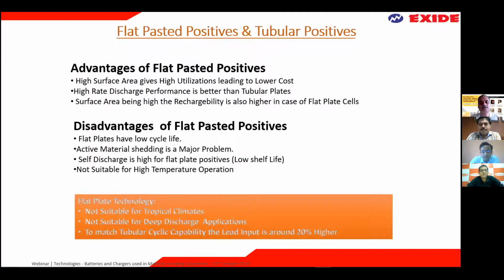Here you can see the basic advantages between a flat pasted positive and a tubular positive. For example, a flat pasted positive, having a high surface area, can provide a very high rate of discharge when compared to a tubular battery. It also provides higher utilization of active material, and because of the high surface area, higher rechargeability. But looking at the negatives, a flat plate has a lower cycle life compared to a tubular battery, because of the major problem of active material shedding. This shedding, coupled with self-discharge of flat positives, makes them generally unsuitable for high temperature operation.